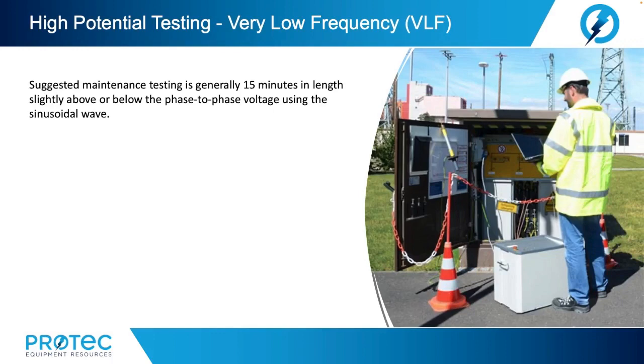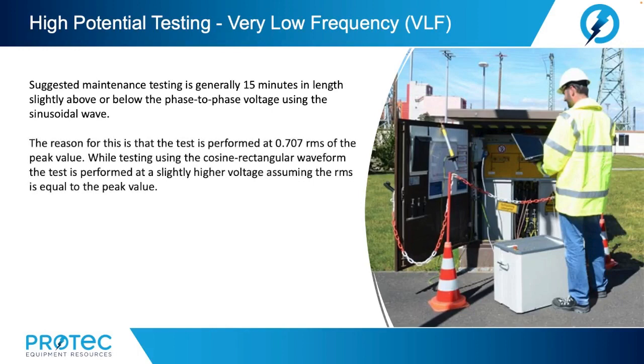Now, suggested maintenance testing is generally 15 minutes in length, slightly above or below the phase-to-phase voltage using the sinusoidal waveform. The reason for this is that the test is performed at 0.707 RMS of the peak value. While testing using the cosine rectangular waveform, the test is performed at a slightly higher voltage, assuming the RMS is equal to the peak value.